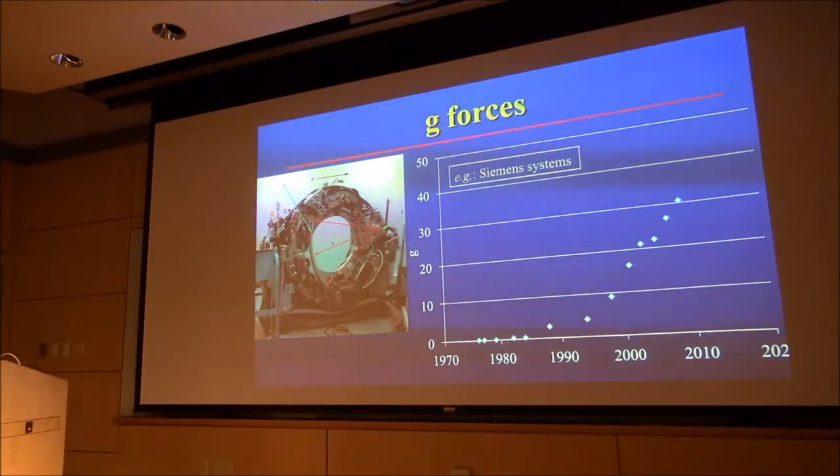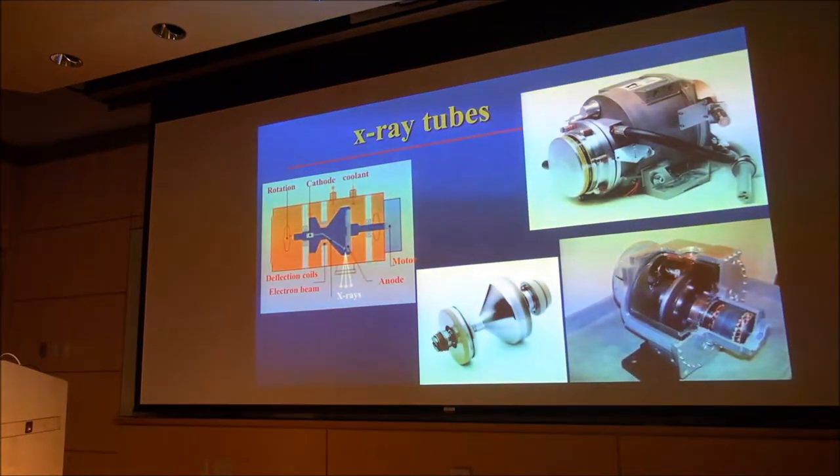The main limit on how fast the CT gantry will rotate is the g-forces on the components mounted on it. This is a plot of the g-forces on the x-ray tube. As this thing rotates these parts are trying to fly off the gantry. We're sitting here now at 30 g's. That's the force on the x-ray tube of a CT scanner. This is much higher than the g-forces on an astronaut during takeoff of the space shuttle.